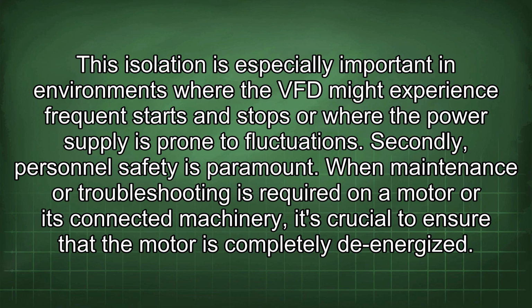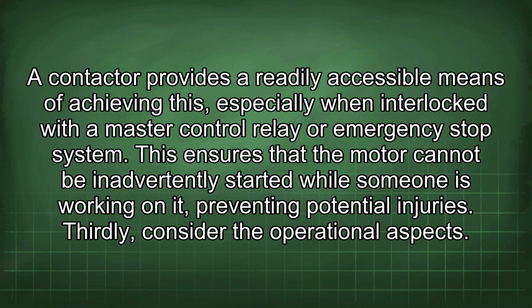Secondly, personnel safety is paramount. When maintenance or troubleshooting is required on a motor or its connected machinery, it's crucial to ensure that the motor is completely de-energized. A contactor provides a readily accessible means of achieving this, especially when interlocked with a master control relay or emergency stop system. This ensures that the motor cannot be inadvertently started while someone is working on it, preventing potential injuries.